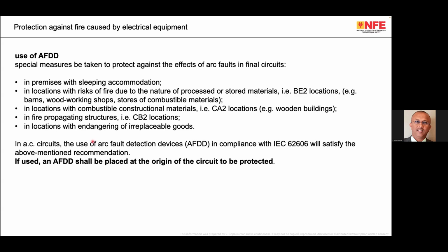There is a device called AFDD, which is recommended in NEC. AFDD stands for arc fault detection device. Now, there is a small difference of recommendation between IS 732, basically IEC 60364, and our National Electrical Code. In IEC 60364, the AFDD is recommended in premises with sleeping accommodation, meaning where you have bedrooms. In NEC, it's a little bit more clear. You'll be able to see that in the next slide.